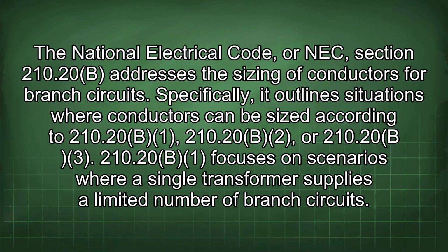The National Electrical Code, or NEC, Section 210.20(B) addresses the sizing of conductors for branch circuits. Specifically, it outlines situations where conductors can be sized according to 210.20(B)(1), 210.20(B)(2), or 210.20(B)(3). 210.20(B)(1) focuses on scenarios where a single transformer supplies a limited number of branch circuits.